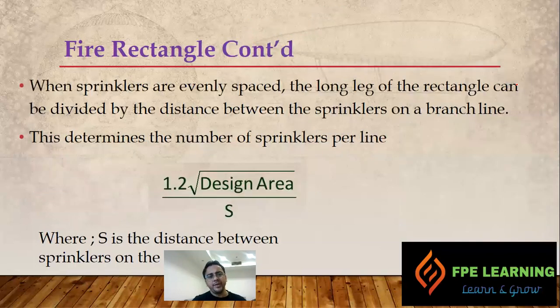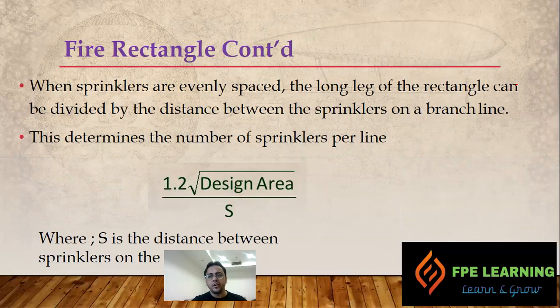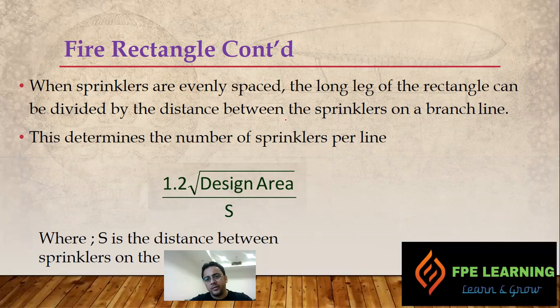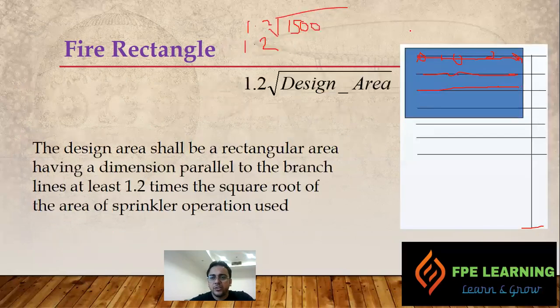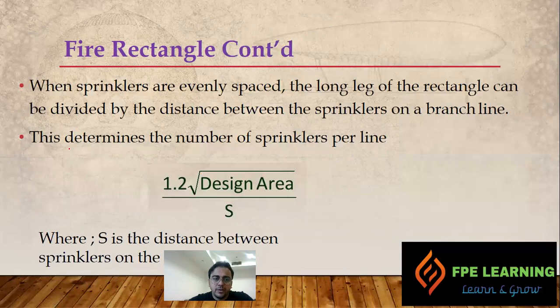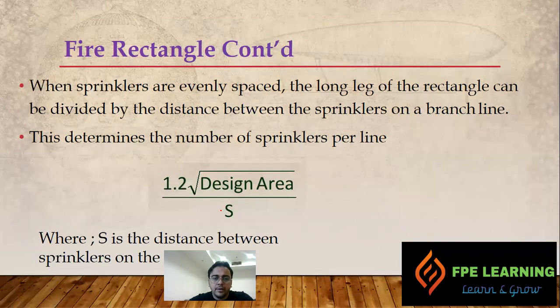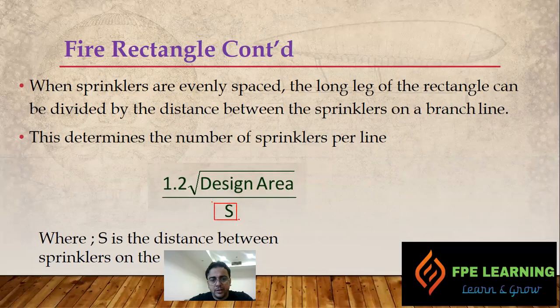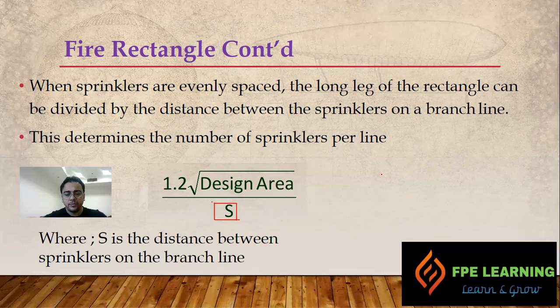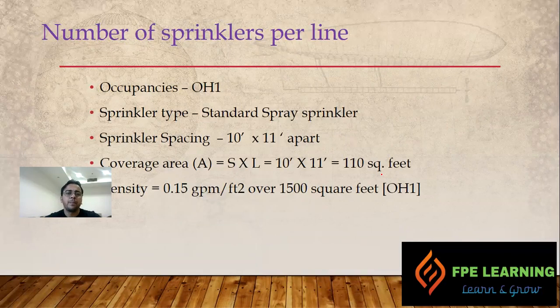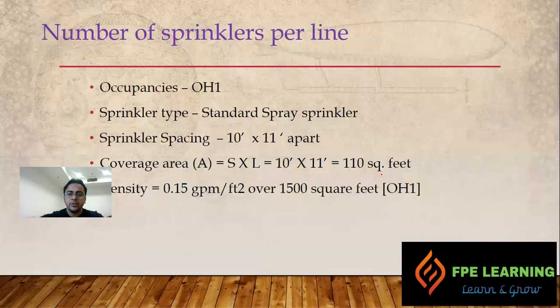When we locate sprinklers evenly, the long leg of rectangle can be divided by the distance between the sprinklers on a branch line. This formula determines the number of sprinklers per line. If you put 1.2 multiplied by square root of 1500 for OH-1 and S is the maximum distance between two sprinklers, we can come to some values.